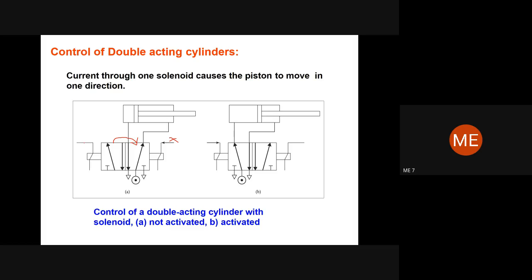Right. Now in this case, what type of cylinders you need to choose is very important. In case of the hydraulic cylinder, the choice of cylinder is going to be very important. You know, pressure is equal to force by area. So the force which is going to be required is equal to the pressure of the hydraulic oil that you are going to place, and also the area of the cylinder. Therefore, area of the cylinder is going to play a major role.